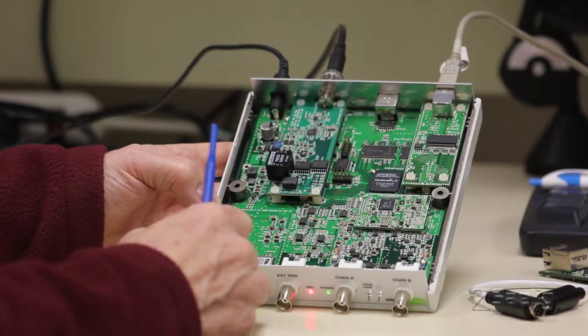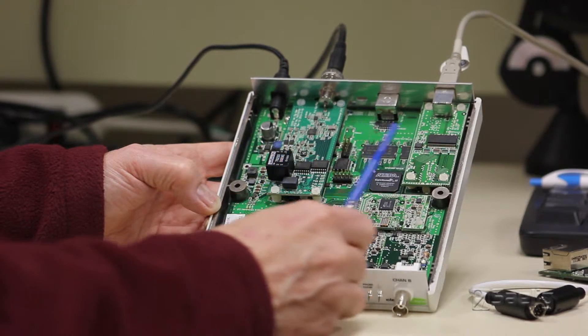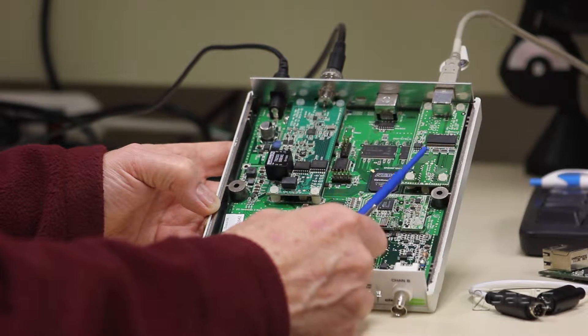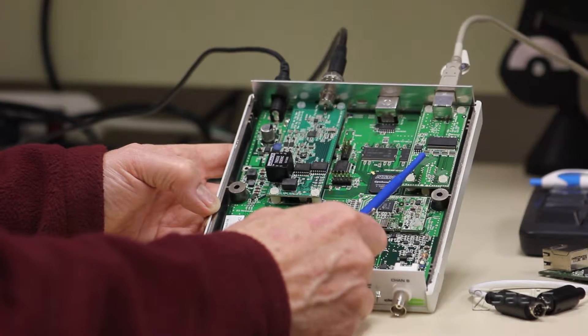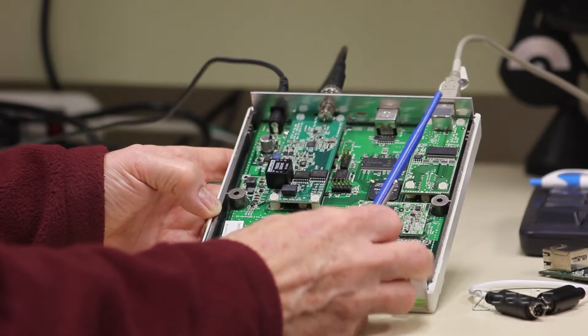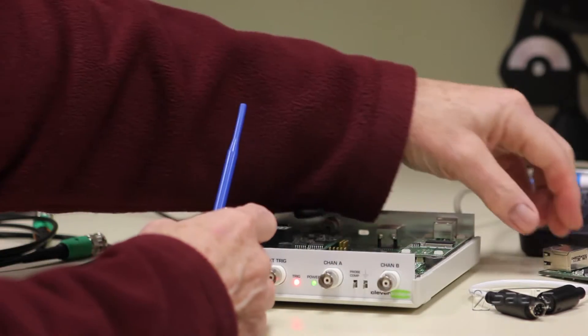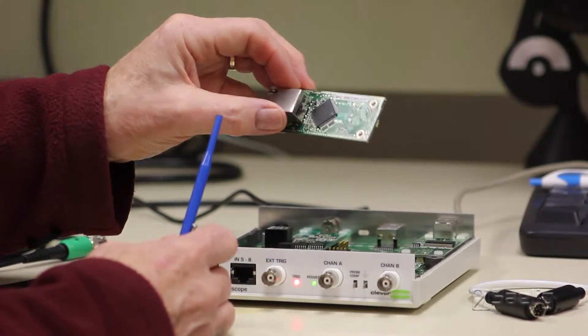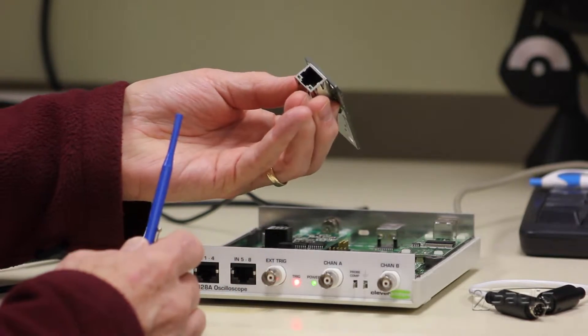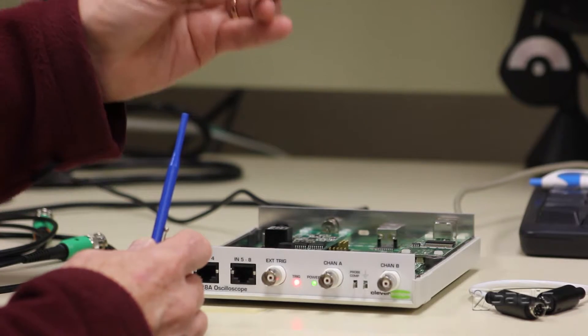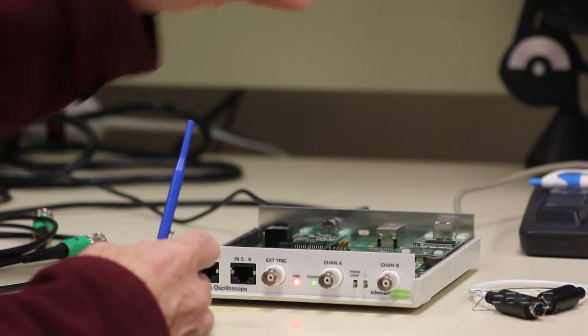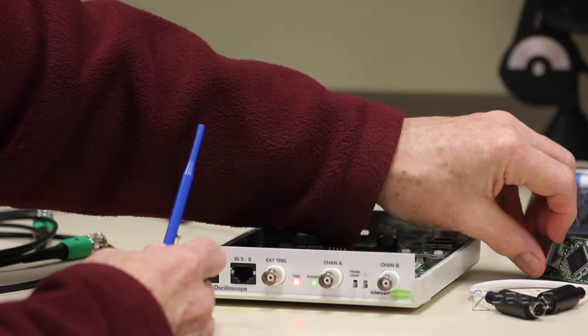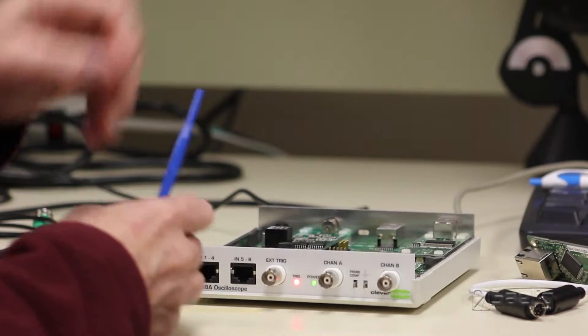The second thing is whether you have USB or Ethernet. This particular scope here is a USB connected one. If you need to have Ethernet, we can install this Ethernet module right here in its place. It requires a different back panel and there's a little extra work involved, so it's not something we recommend as a customer upgrade.